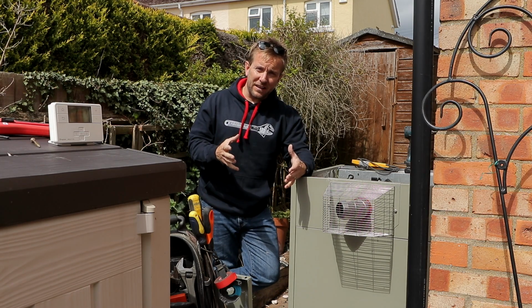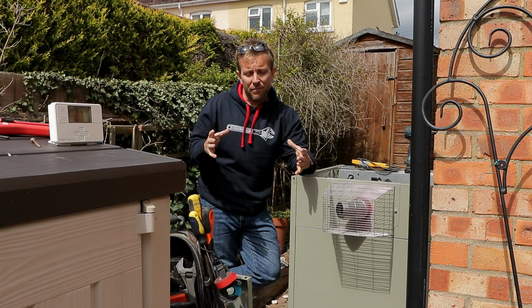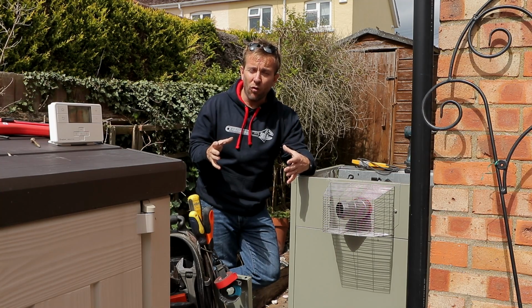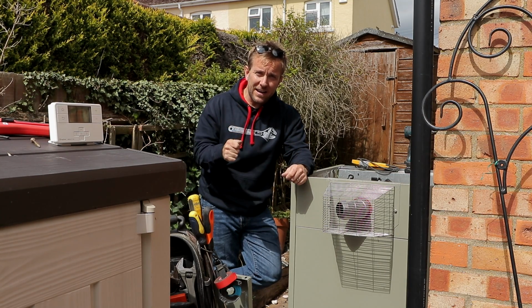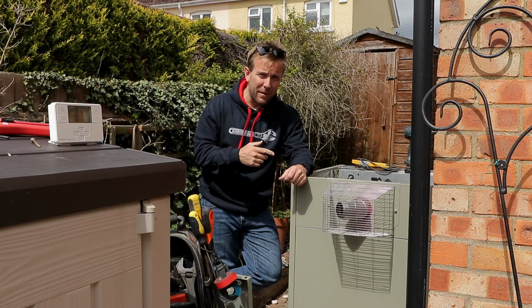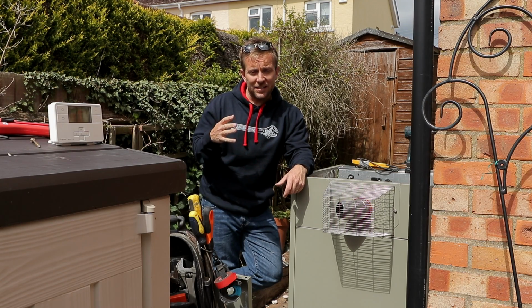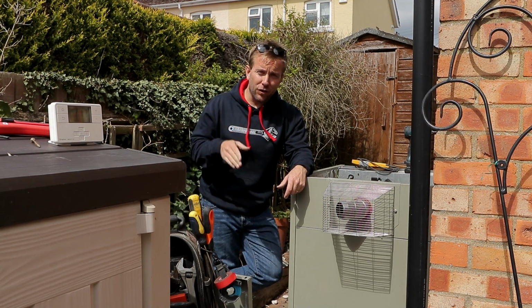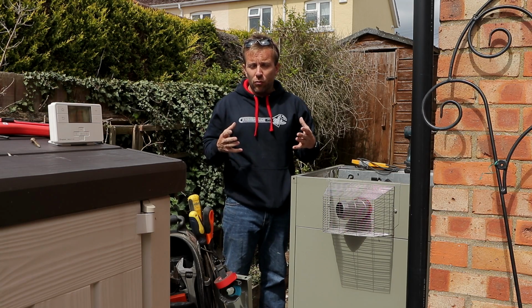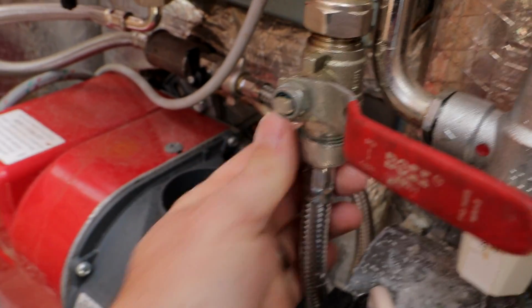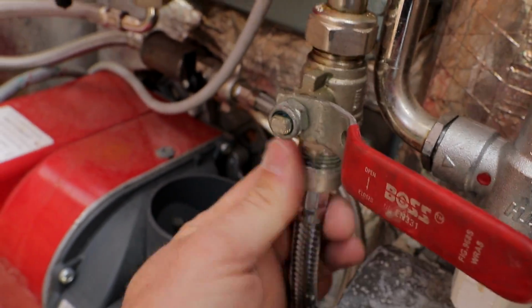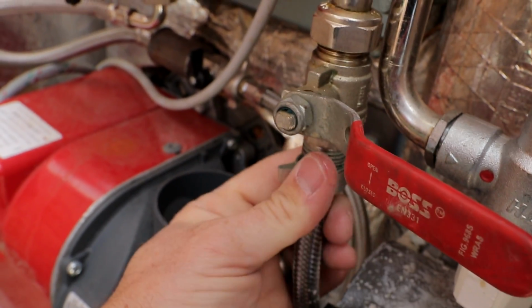Now I've checked a few other things as well to make sure they're okay, like making sure the expansion vessel is alright. Also, I've taken off the braided hose off the front of the boiler, and I'll show you that in a minute, and I've made sure there's no let-by from the two fill valves, because on combi boilers we're on a pressurized system, we've got a braided hose, and we want to make sure those valves are shut and the braided hose is taken off.